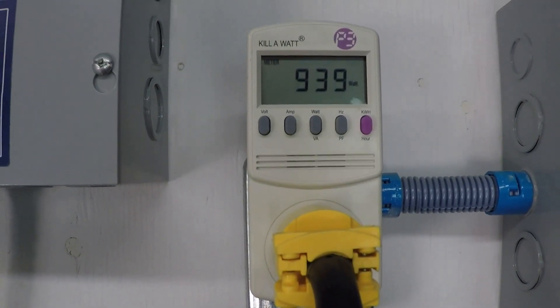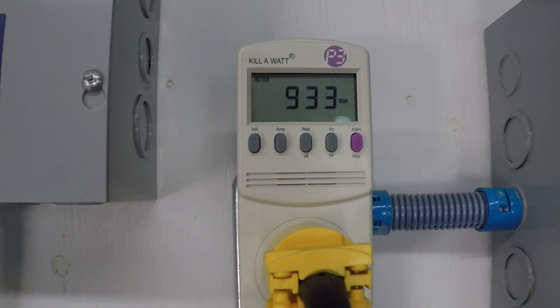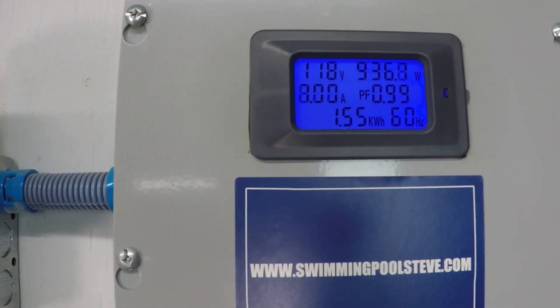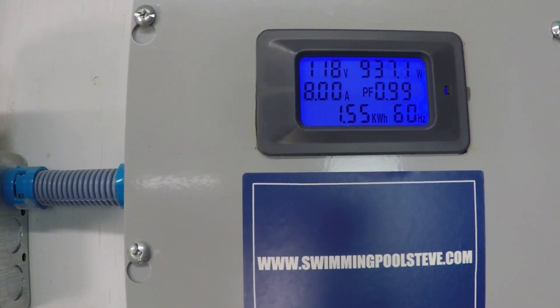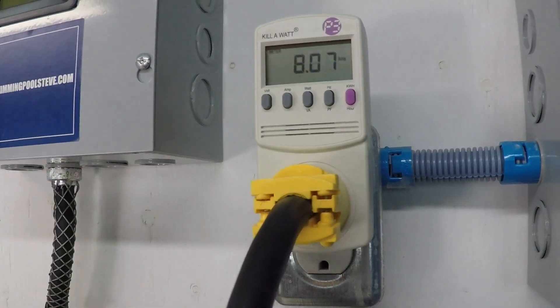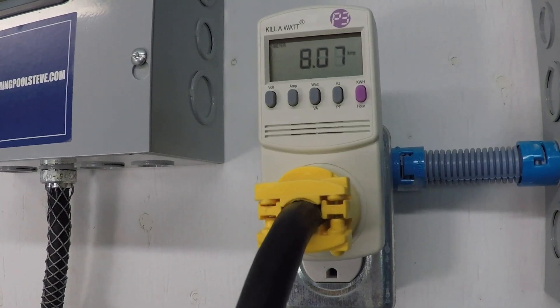Just over 70 gallons per minute. About 930 watts. Almost exactly 8 amps there. 8.07.